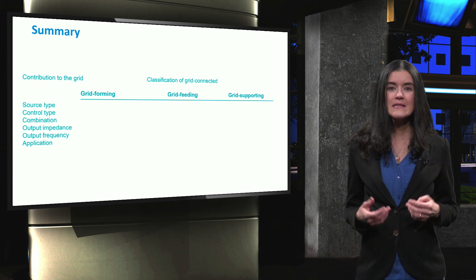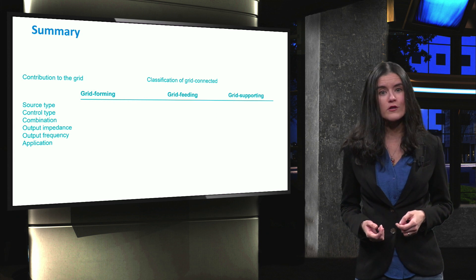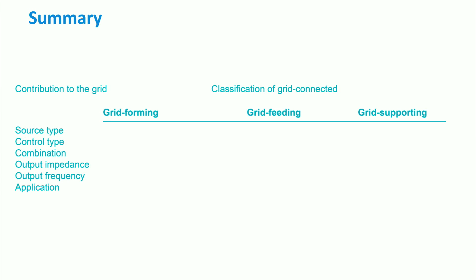So to sum up, let's now take a look again at the characteristics of the three types of converters. The grid-forming type is represented by an ideal voltage source, and its control is based on a constant frequency and voltage strategy. The output frequency is a fixed frequency. This means that the frequency is given by the converter and not imposed by the grid. The main application of this type of converters is islanded mode.